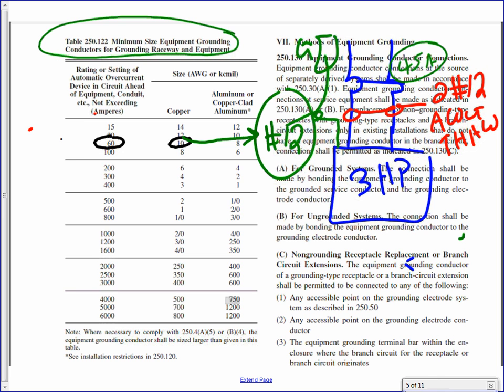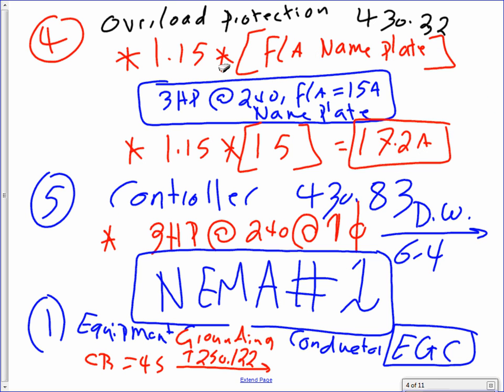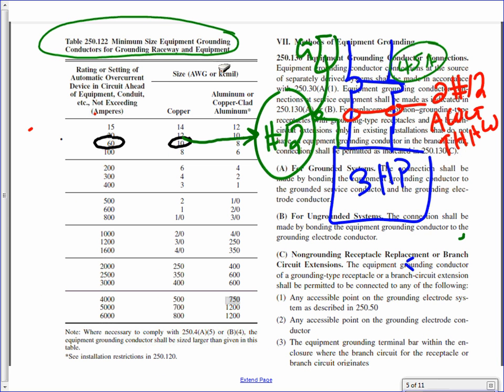Can you guys see that? Okay, I can go 15, 30. My next standard is 60. I have to go up. 60 will give me what size? Number 10. 60 will give me size number 10. So what size equipment ground conductor do I need? One conductor, number 10 AWG THHW. There's one little problem though. The size of the branch circuit conductor, what size is the branch circuit conductor? 12. The equipment grounding conductor is number 10.